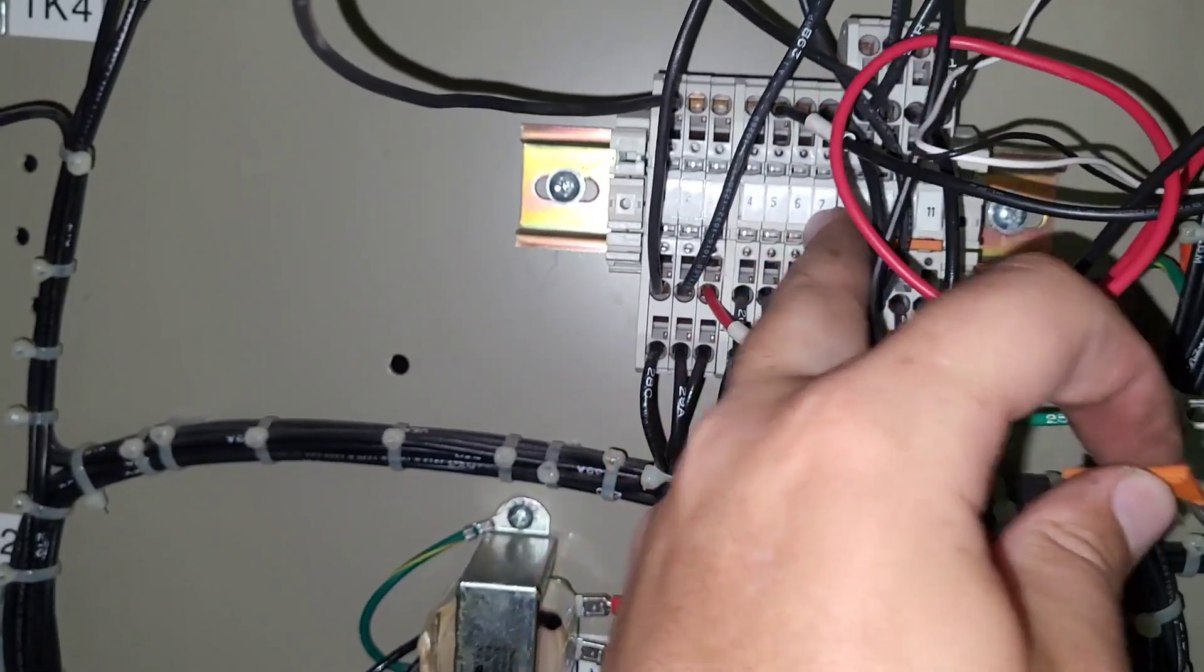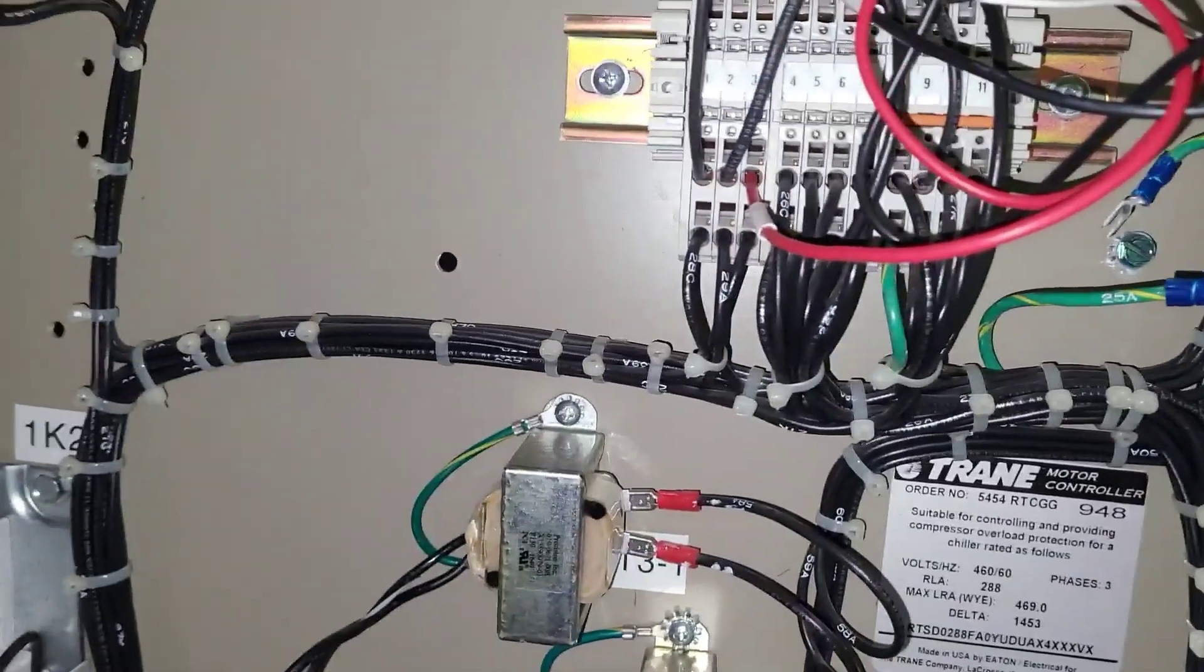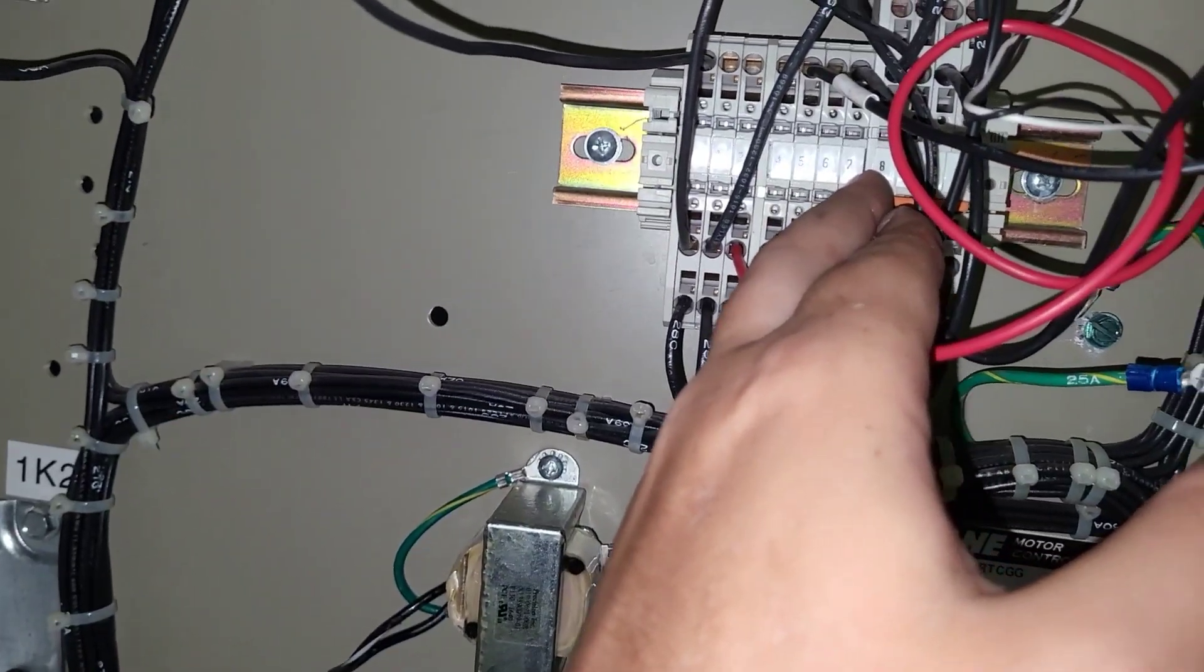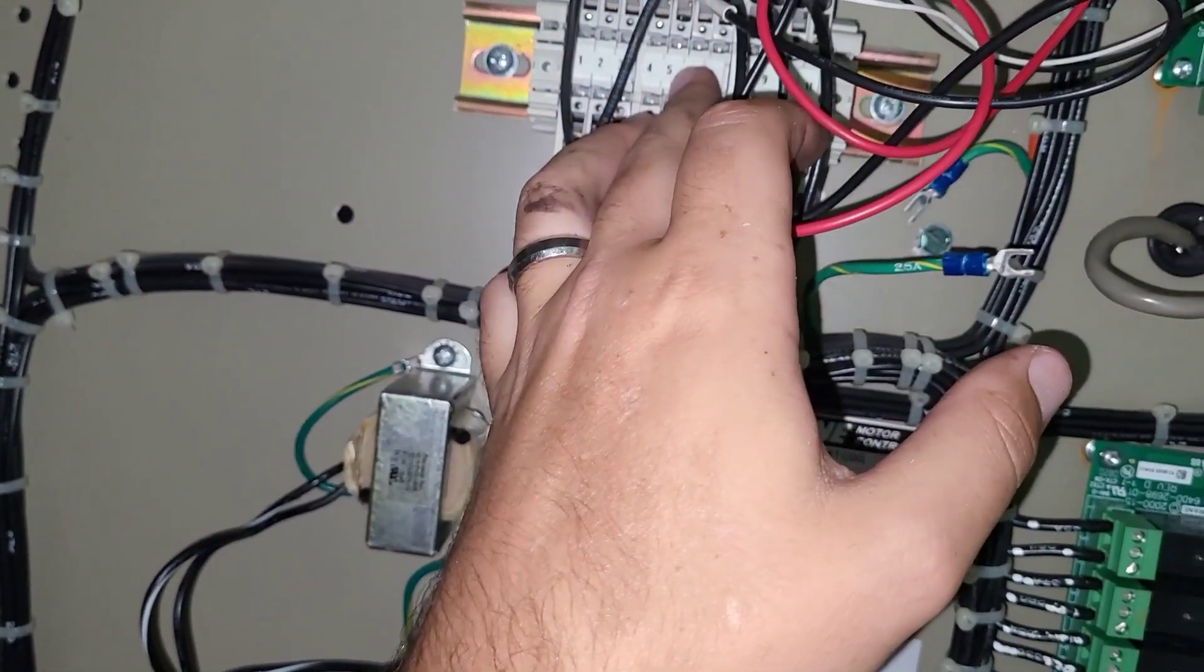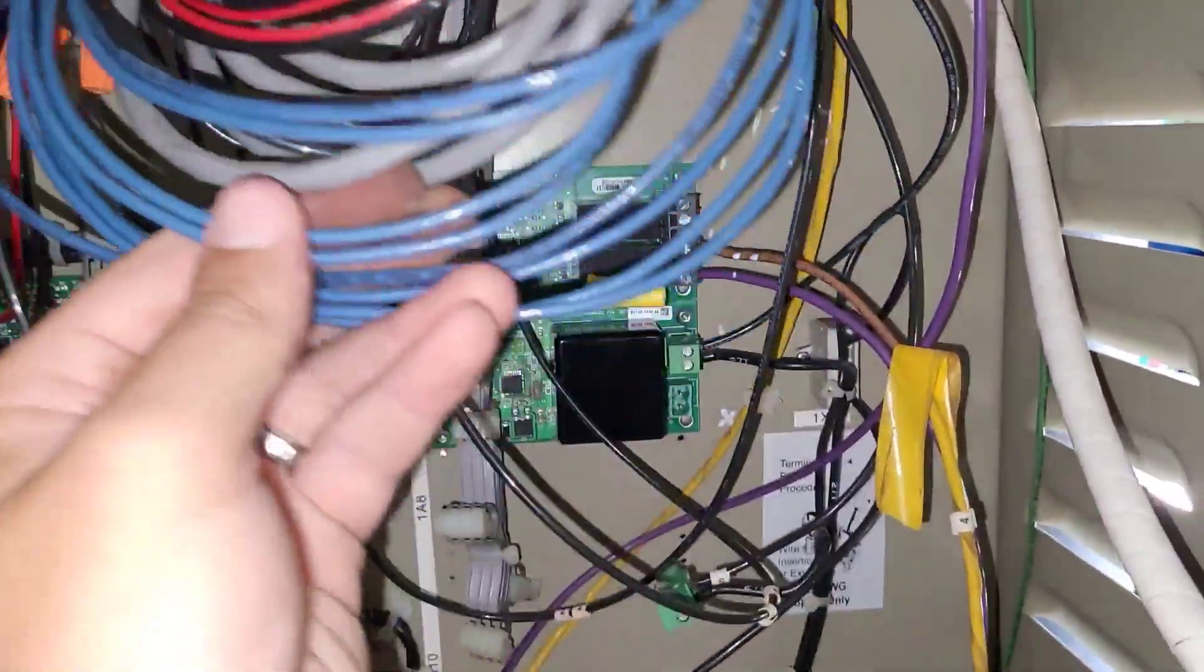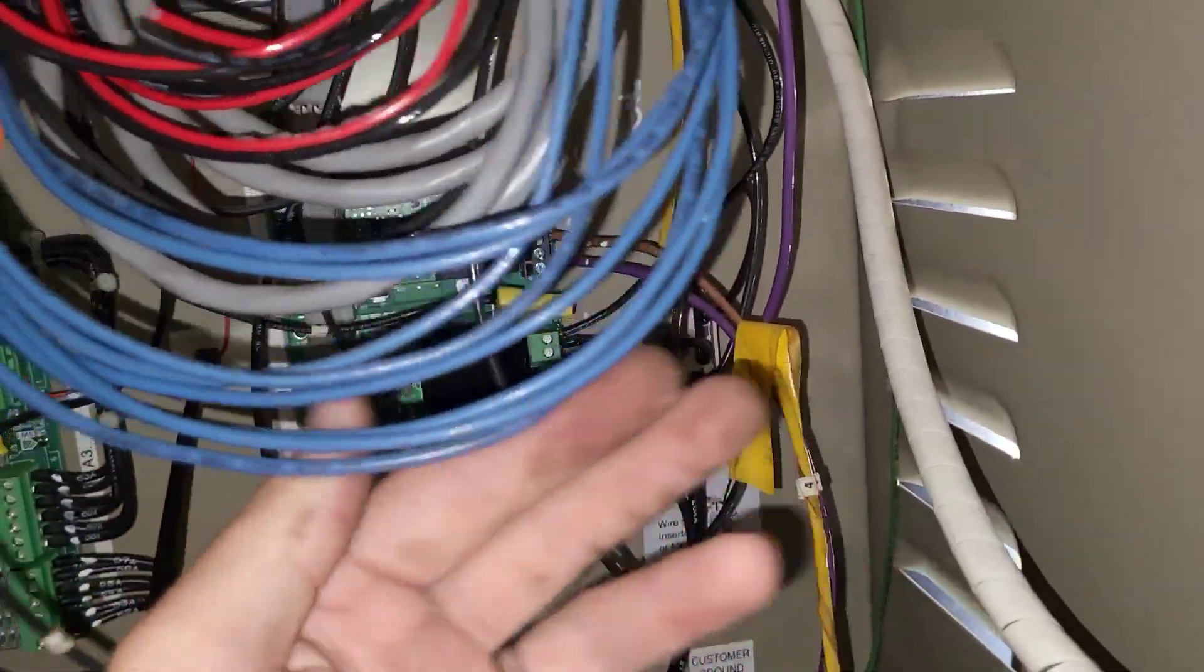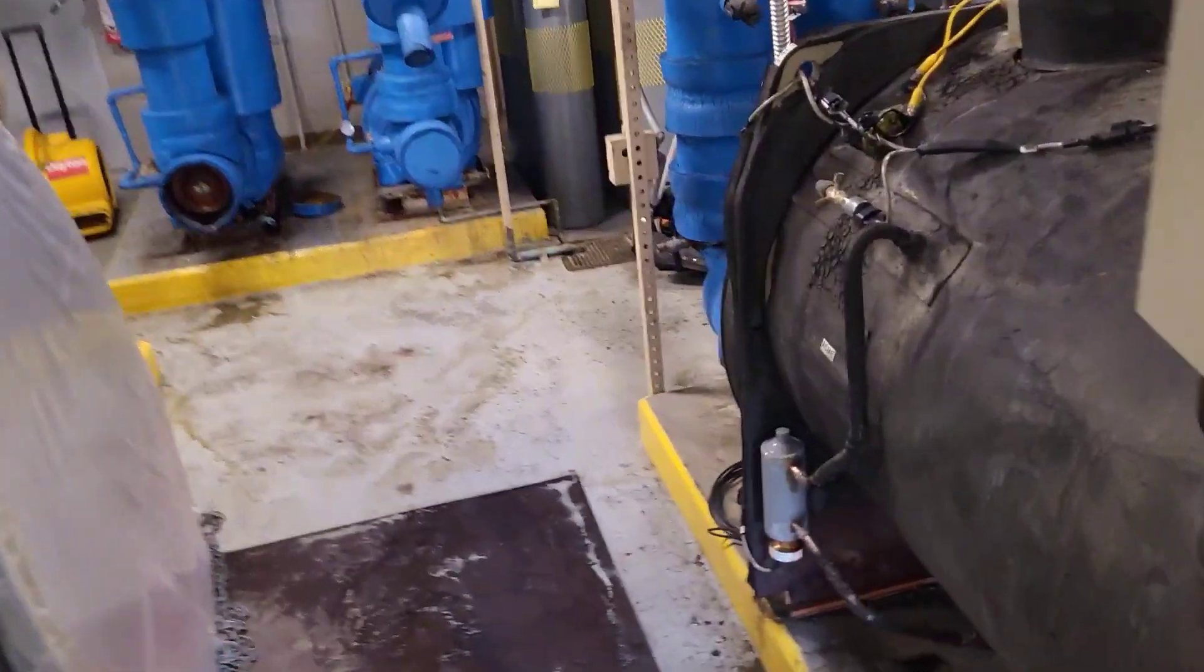I wanted to identify which one of these specific circuits is actually the one shorting, so I pull the jumper out and I start testing each one of these to ground individually. I test circuit seven to ground and it shows the direct short. All the rest of them check good. Then I pull up the schematic and I start going through the schematic and I see that circuit seven goes through my flow switches. That led me back over here and I tested the chill water flow switch at first because that's just where I started, and I saw a short to ground through the chill water flow switch.